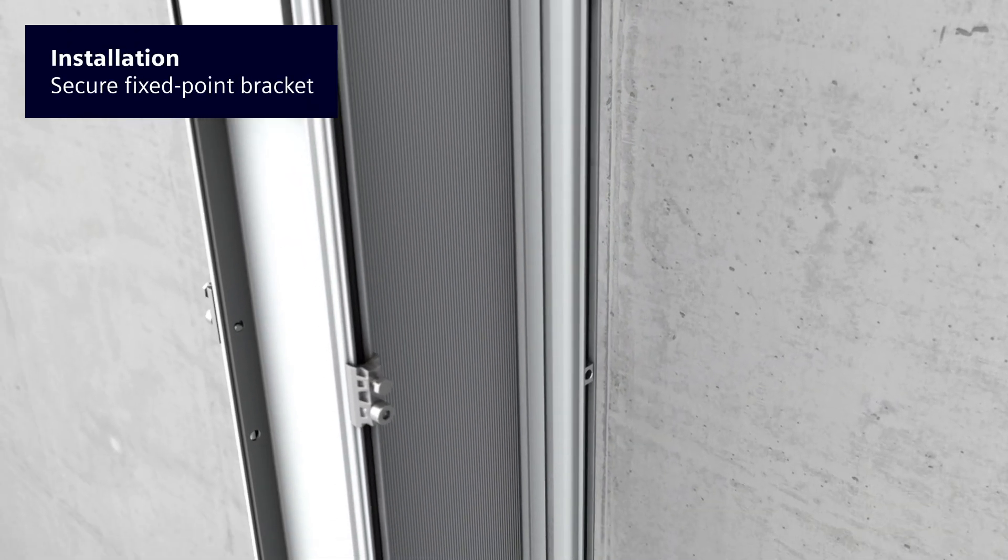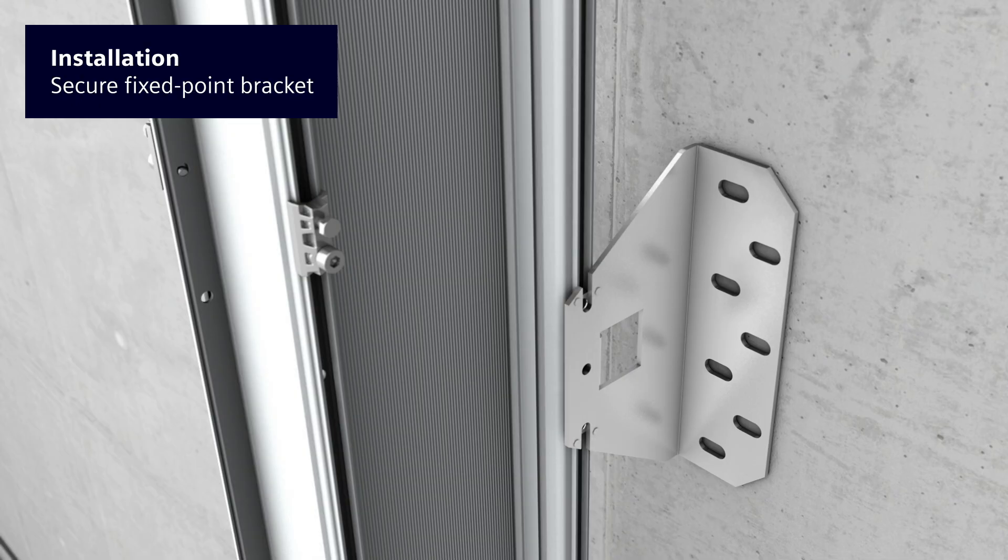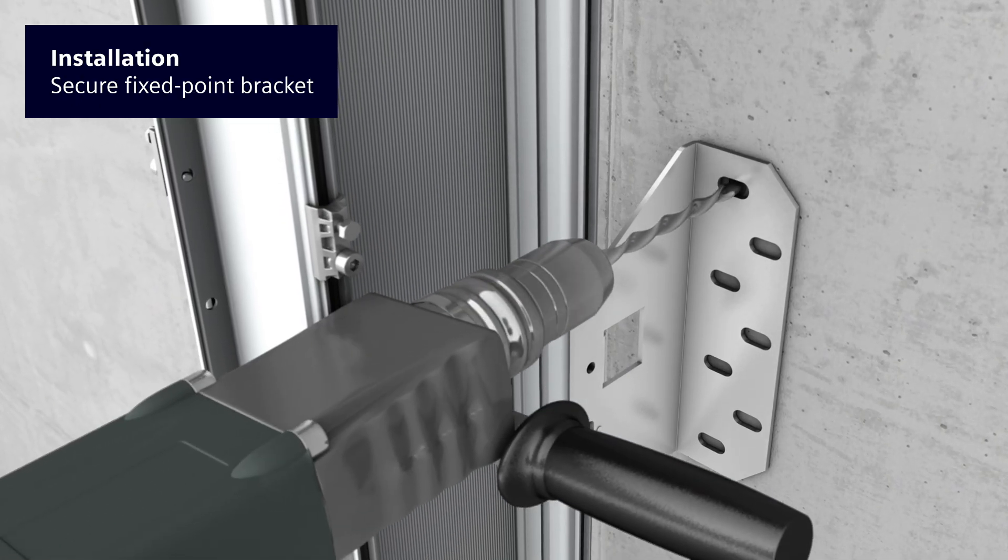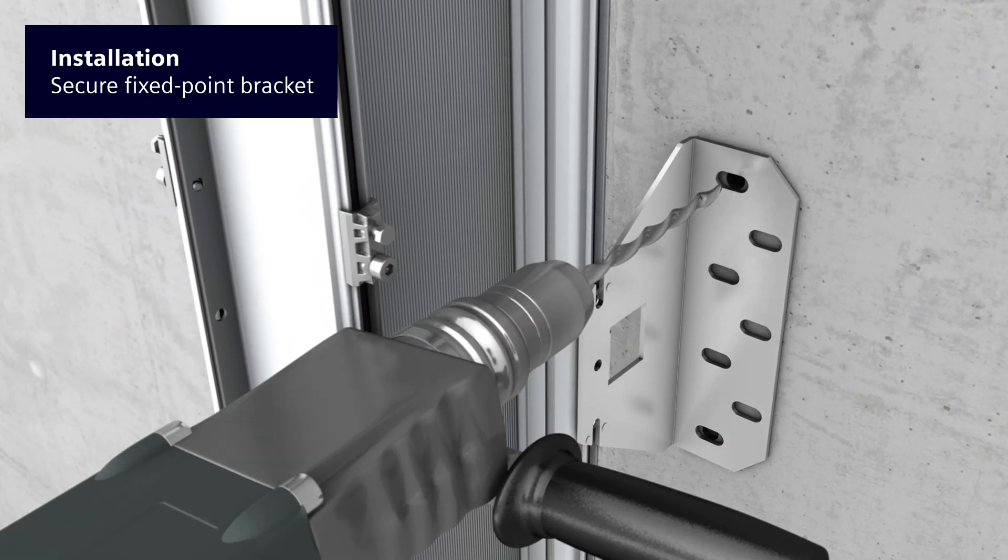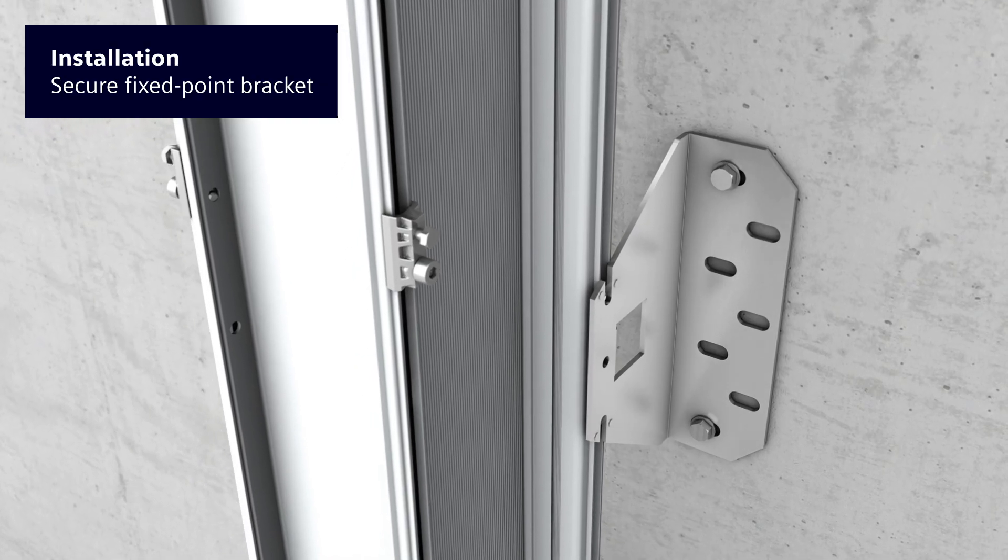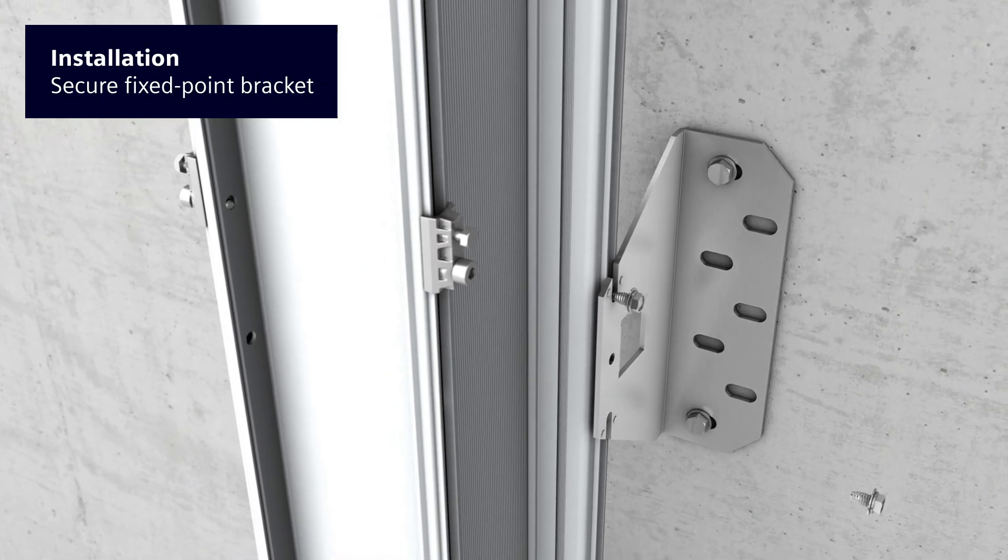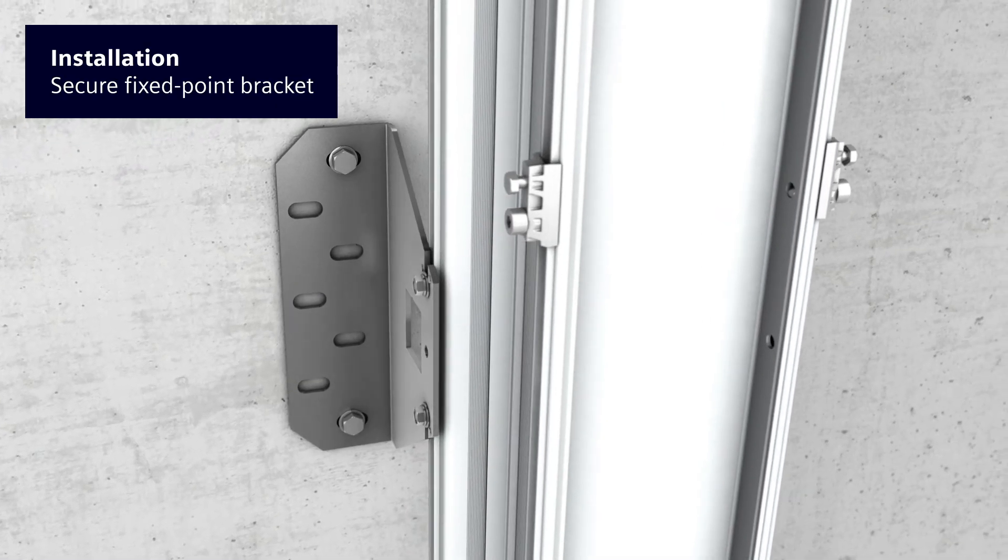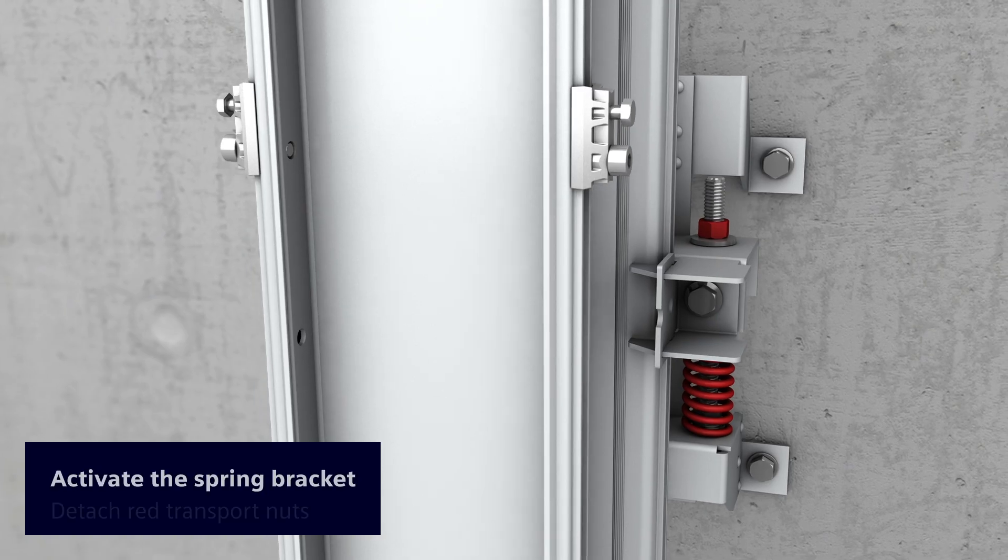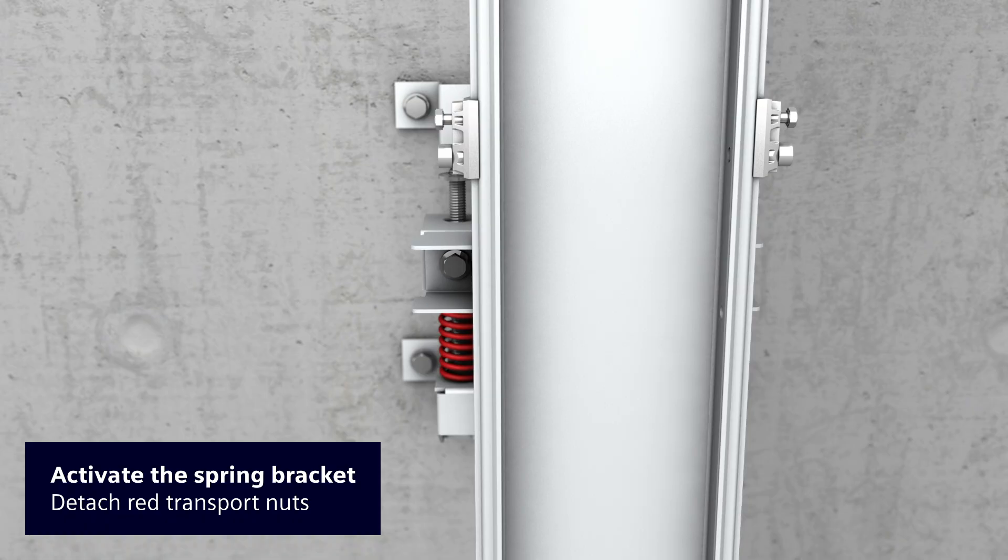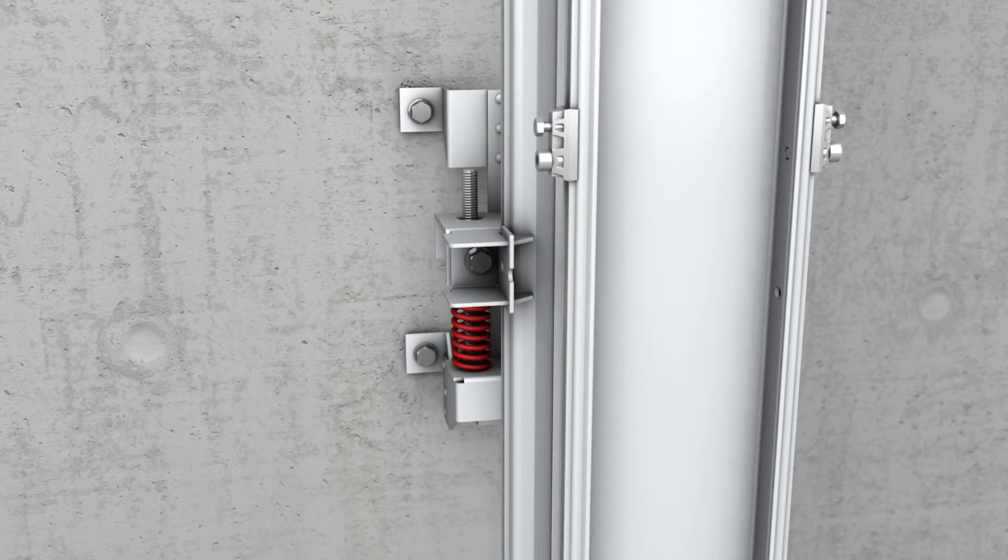The fixed point bracket is an important retaining element in vertical installations. The fixed point bracket serves as a template for drilling the fixing holes in the wall. Once the holes have been drilled, the fixed point bracket is then screwed to the wall and to the trunking unit. The spring bracket becomes functional with the removal of the red nuts for transport protection.